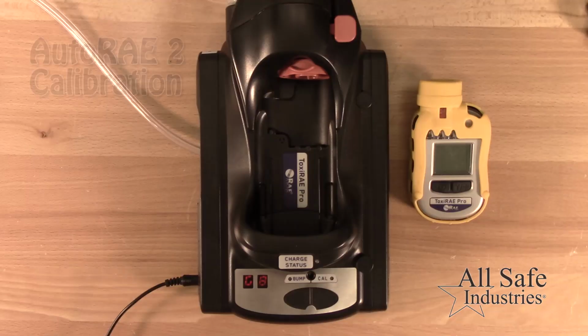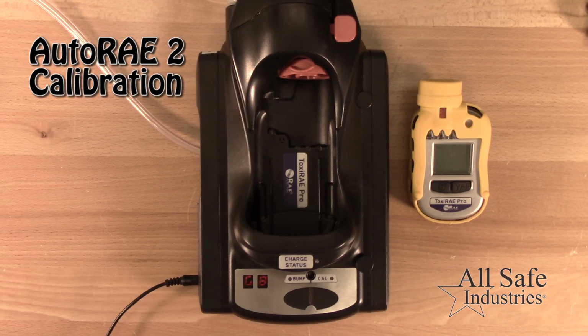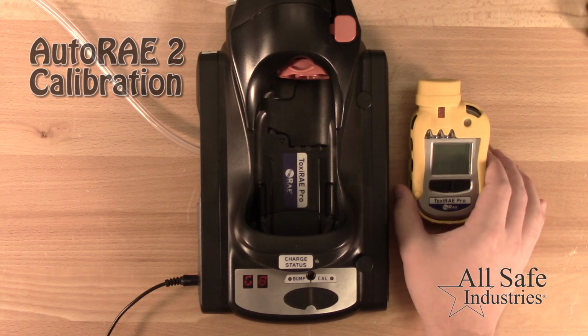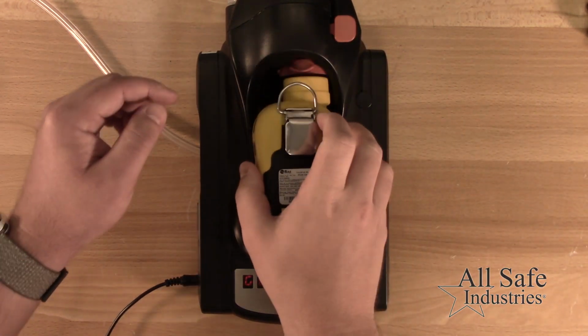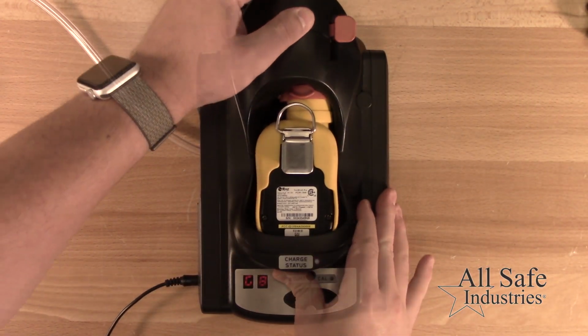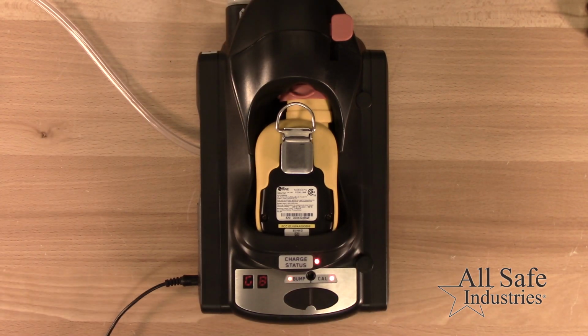To calibrate using an AutoRAE 2 calibration cradle, start with the ToxiRAE Pro turned off. Place the meter face down on the cradle and close the capture mechanism. This will power up the meter and begin the warm-up sequence. Once both lights are solid green, press the cal button. Once the calibration is complete, the cal light will display solid green for pass or solid red for fail.